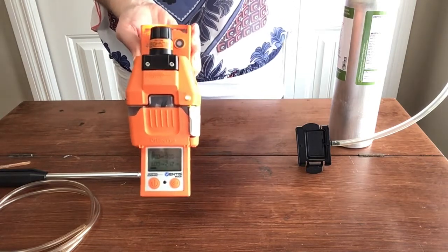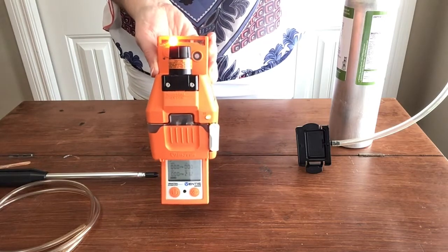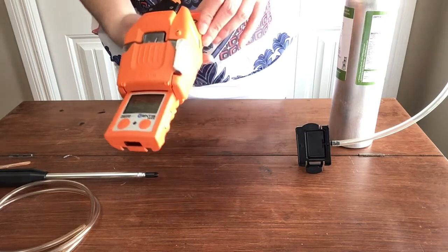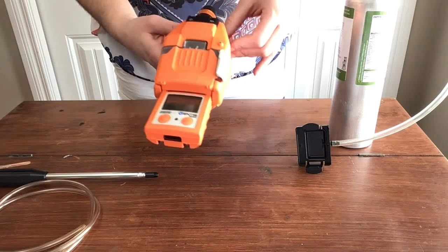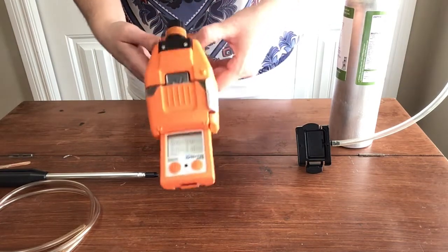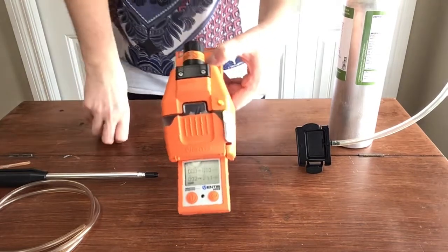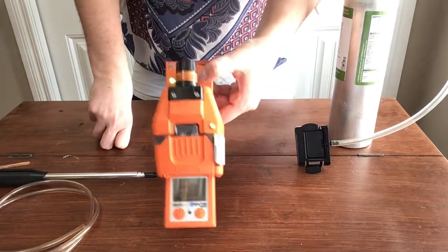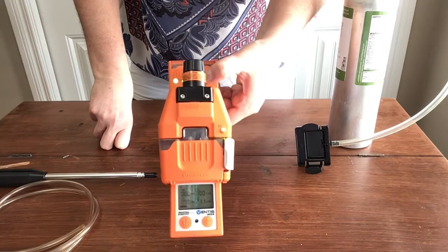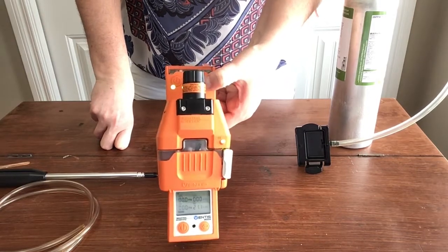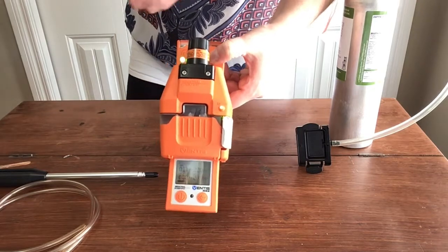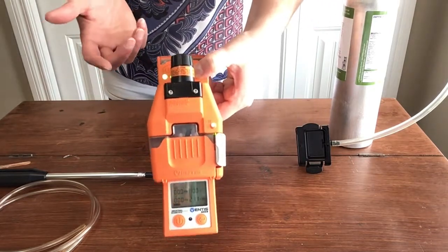This one also has sensors on it. Those will be them, okay? Sorry, I'm just gonna put this over the audible alarm here. So this one also has sensors on it, and it needs to check those sensors before you use it as well. So you should be able to hear that or feel that vibration, and you should be able to see those lights and hear the audible sensor that you just heard, okay? So the pump is running.